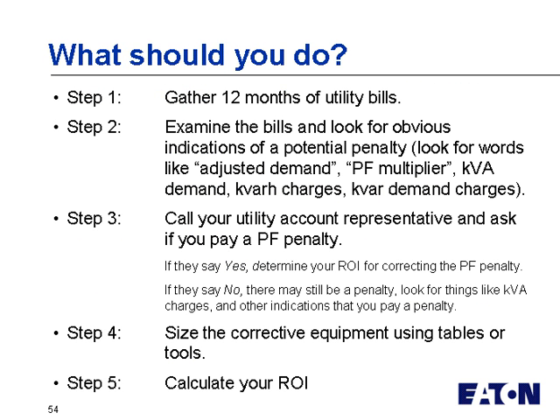Well, our suggestion would be that you should take about 12 months' worth of utility bills, and as we learned in our own facility, the winter and summer months may be dramatically different. So it's important to look at 12 months. You should examine the bills and look for obvious indications, as we just pointed out, things like power factor multiplier, kVA rates, kVAR charges, kVAR demand charges, things like that. Adjusted demand, things that don't necessarily jump out at you, say, like a power factor penalty.